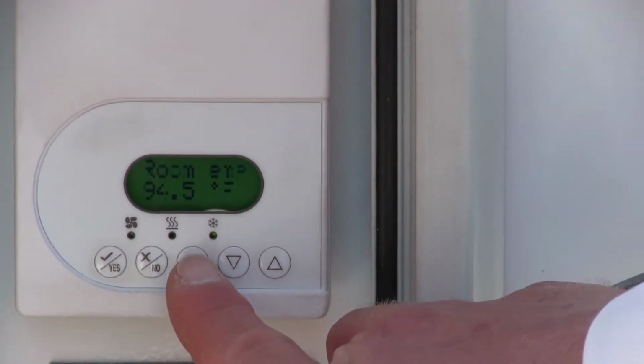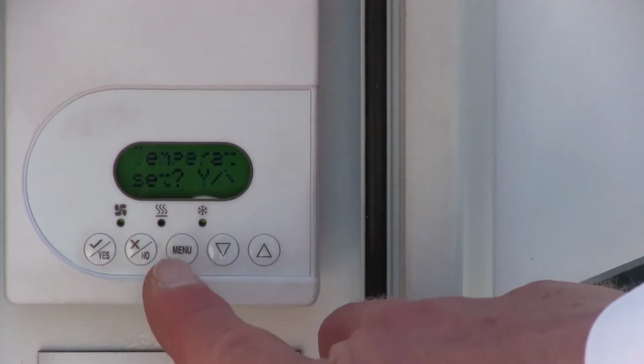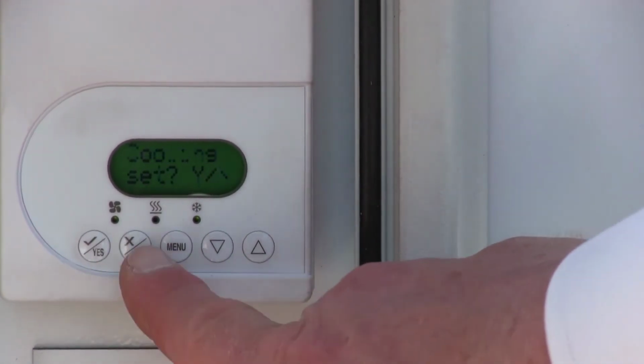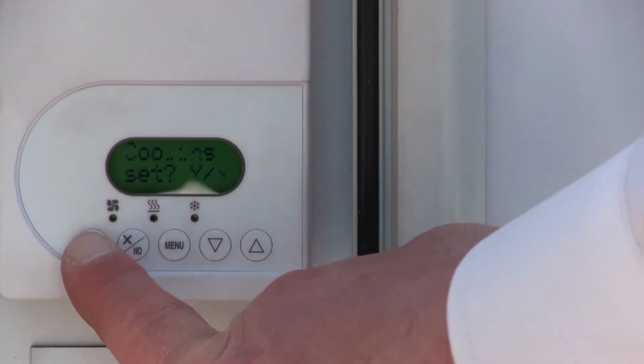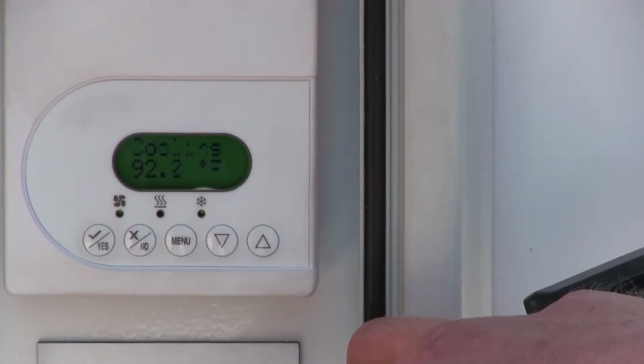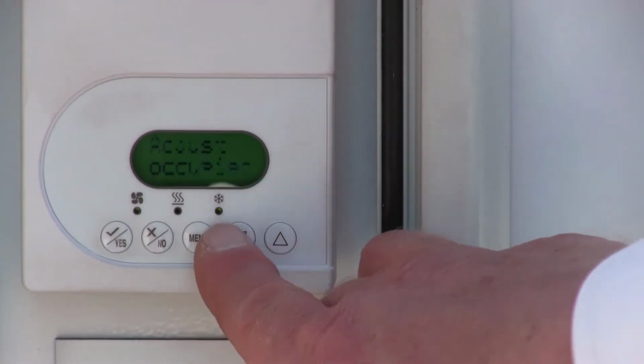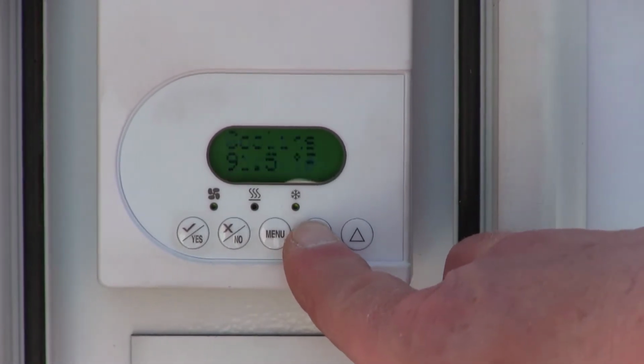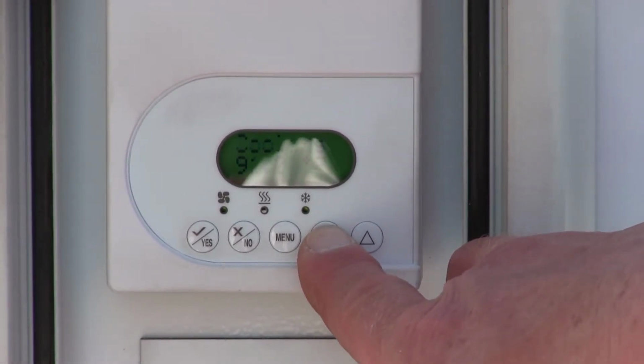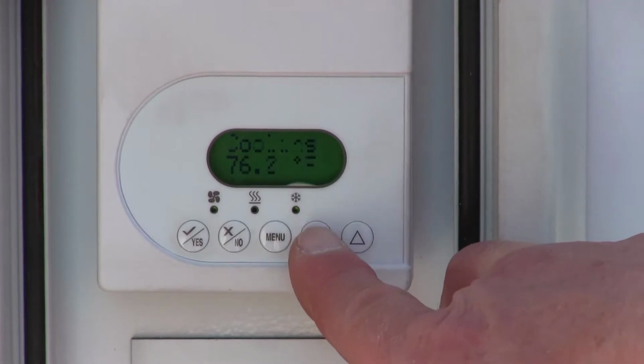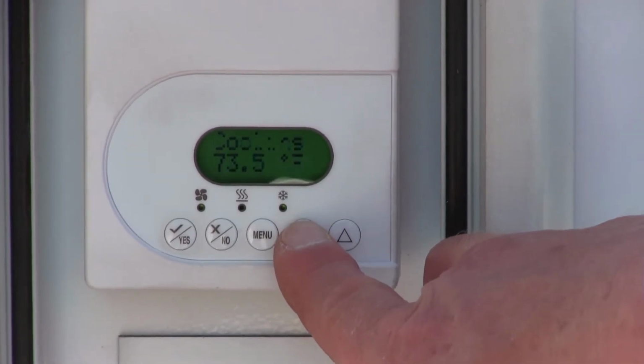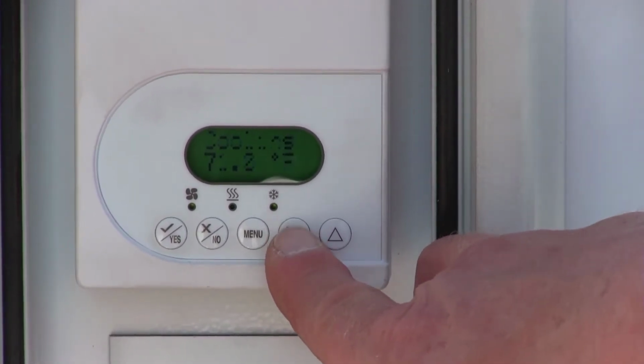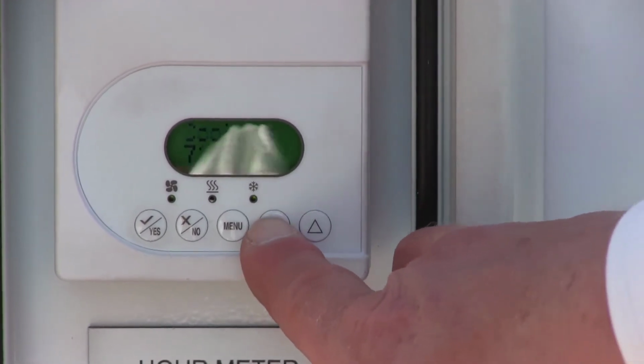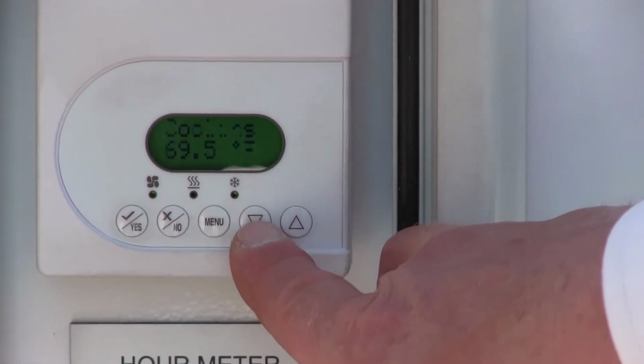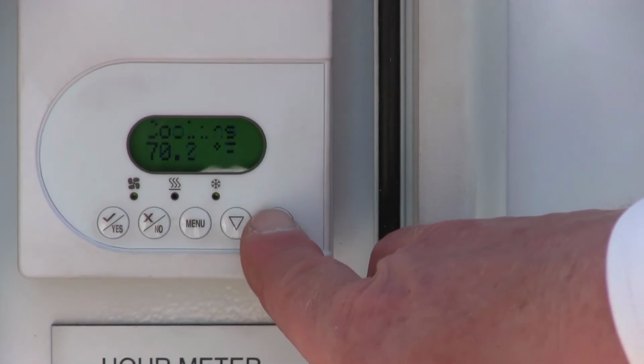Then we're going to go back to our menu again and push it and say, this time we want to set the temperature, yes. And we want to set the cooling, yes. And our current cooling is set for 92.2. We're going to lower that down to 70 degrees. And we're just going to set 72 degrees. You're going to hold it for rapid or go slower by each button punch. There's 73.5. And there's 72 right there. That's right, 70 degrees. We'll leave it at 70.